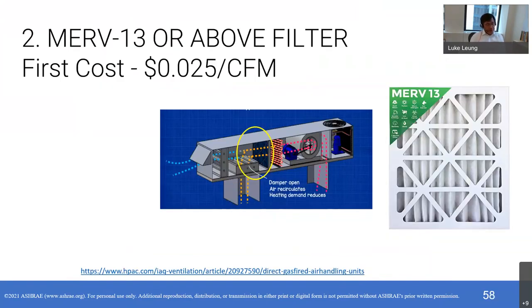But for the MERV 13 filter, the first cost is really low. You can see on the screen right now, it's about $0.025 per CFM. This is based on roughly less than 10 studies. It's not exhaustive, but we have about 10 data points. Many of the projects are in New York, some are in other places. So it's really inexpensive. Next slide.